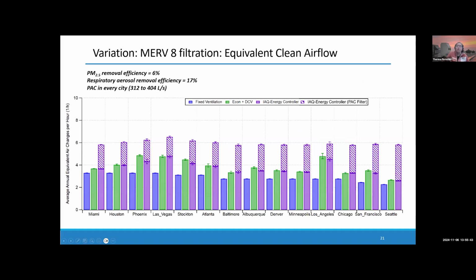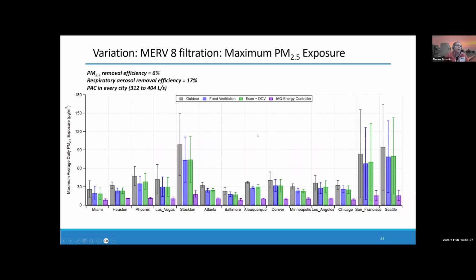And I want to jump back to the MERV 8 filter. If I rerun these simulations, but I have a MERV 8 filter, this is the equivalent clean air flow for respiratory aerosol removals again. And you can see here that the differences now become much more significant in terms of the purple bars are now much bigger than the blue bars because of those small central air handlers. And now the difference between maximum PM 2.5 exposure with a MERV 8 filter is like off the charts, right? So like, for example, in Stockton on these worst air quality days, the amount of indoor PM 2.5 is just astronomical. And the IAQ energy controller sort of makes this manageable in a way it wouldn't otherwise be. So this is like shut down the school versus like we keep going, right?